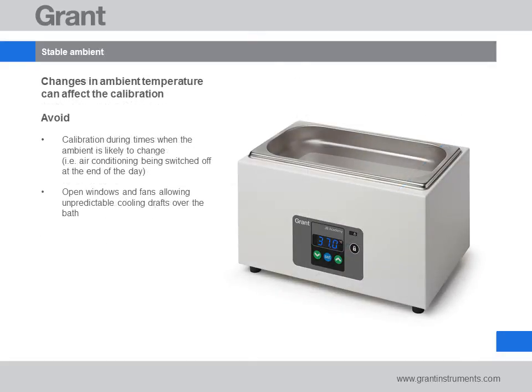For bath calibrations, it's very important to have a stable ambient temperature. For this reason, it's best to perform a calibration at times of the day when the ambient is unlikely to significantly change. It's also important to avoid unpredictable cooling drafts, so ideally set up the bath away from open windows, air conditioning vents and desk fans.